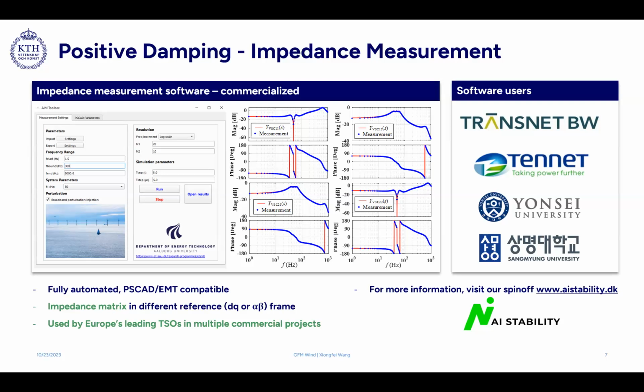Based on our experience with those leading European TSOs, we found that in the frequency range from 0 to 100 Hertz, we cannot use the single input, single output impedance. That is what we often talk about, positive sequence or negative sequence impedance. That is not true. We have to use the impedance matrix to predict the subsynchronous oscillations.